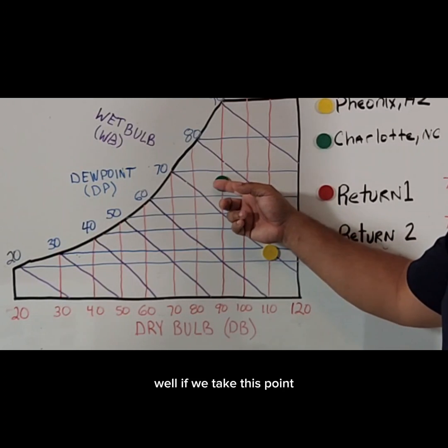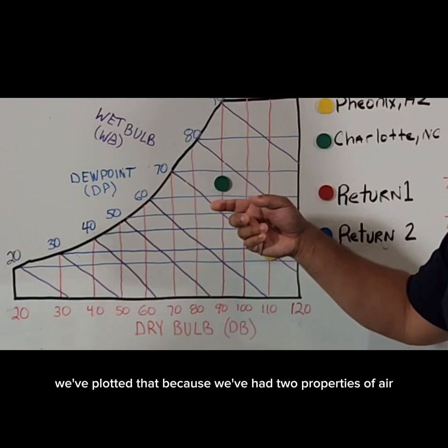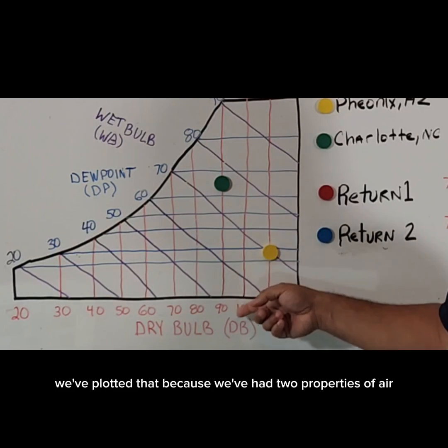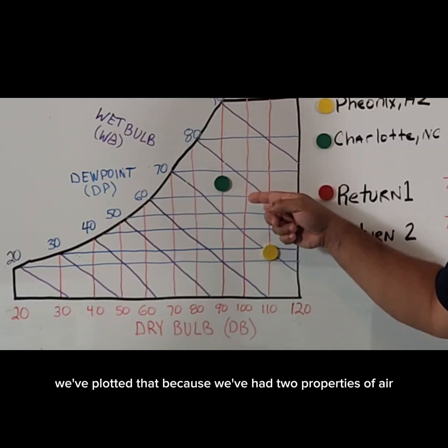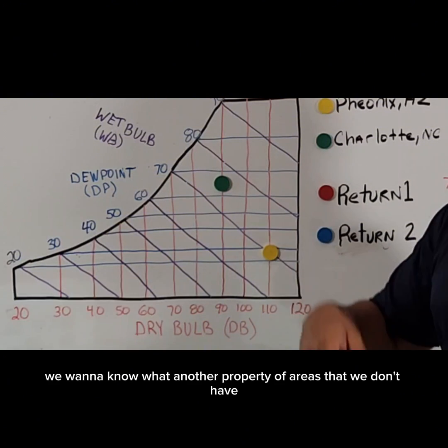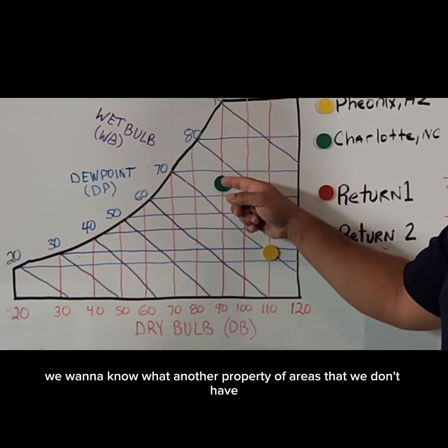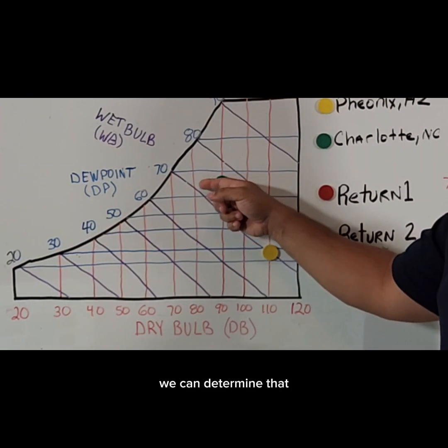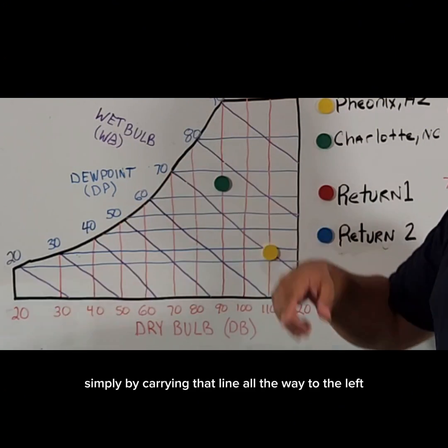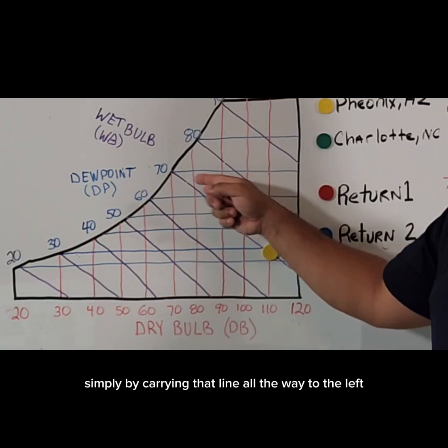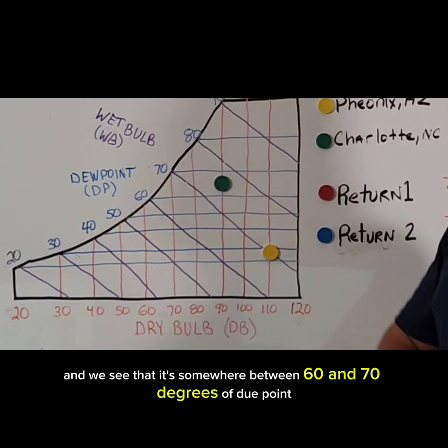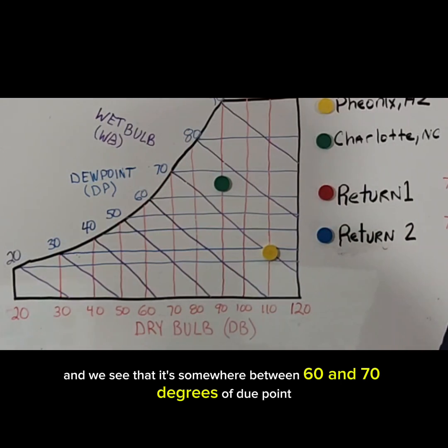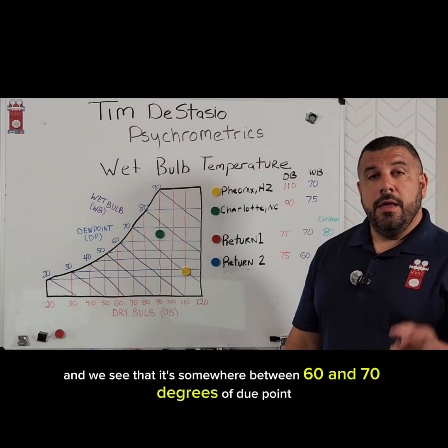Well, if we take this point — we've plotted that because we've had two properties of air — we want to know what another property of air is that we don't have. We can determine that simply by carrying that line all the way to the left, and we see that it's somewhere between 60 and 70 degrees of dew point.